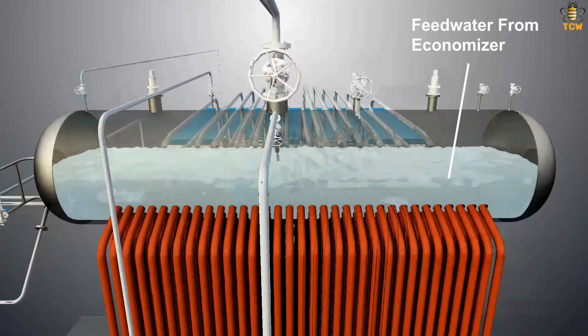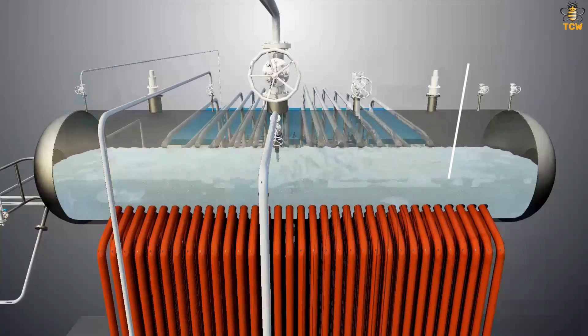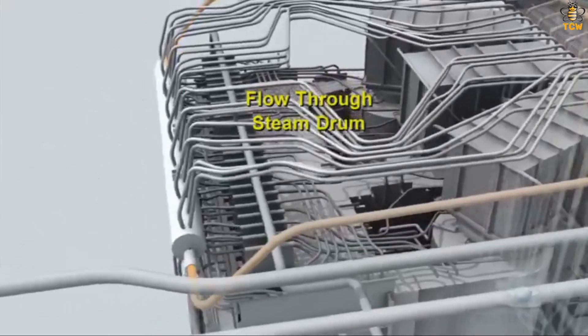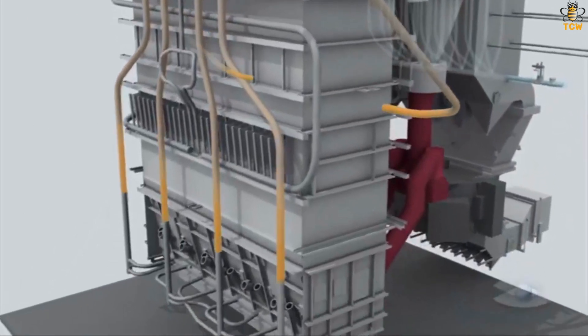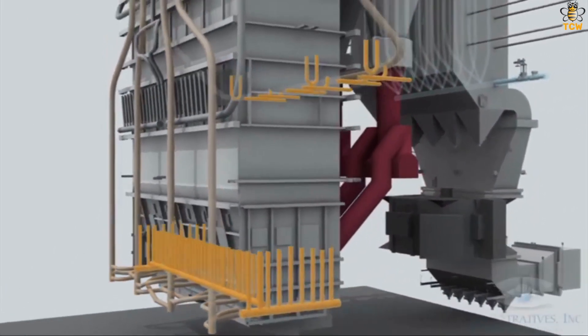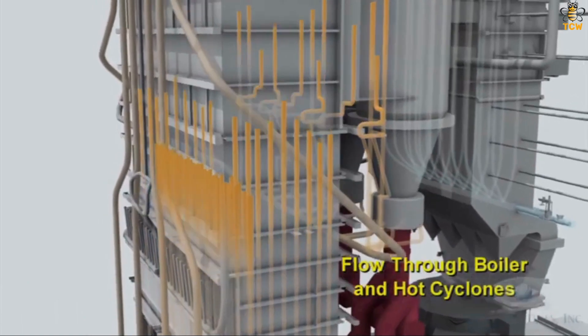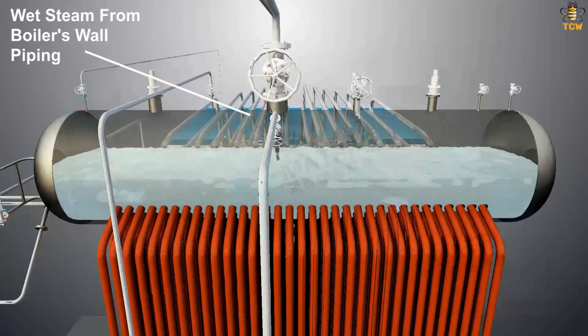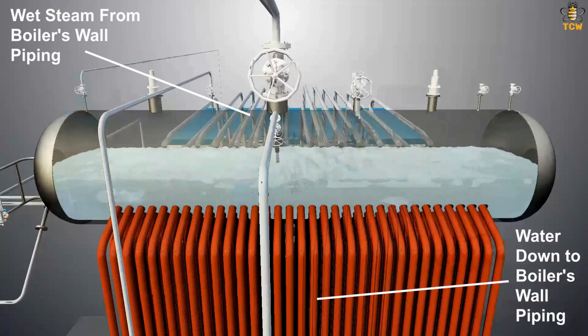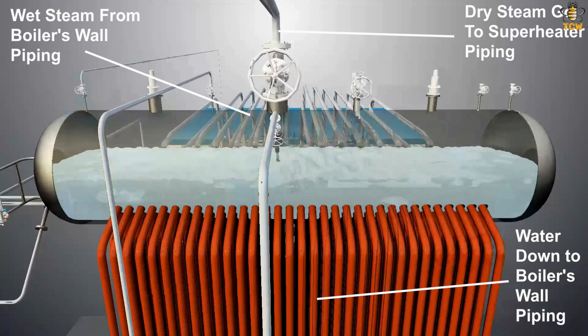In the steam drum, feed water gathers at the bottom of the drum and then flows through brown pipes under the drum. These brown pipes make up the walls of the boiler, so the sides of the boiler are an arrangement of these brown pipes. The feed water in the boiler wall pipes then absorbs heat from the hot gas from coal combustion, boils, and becomes saturated steam or wet steam. This saturated steam is flowed back to the top of the steam drum, where it undergoes phase separation. Water carried by the saturated steam falls and gathers at the bottom of the drum to be heated again, while the drier steam is flowed out to the superheater.